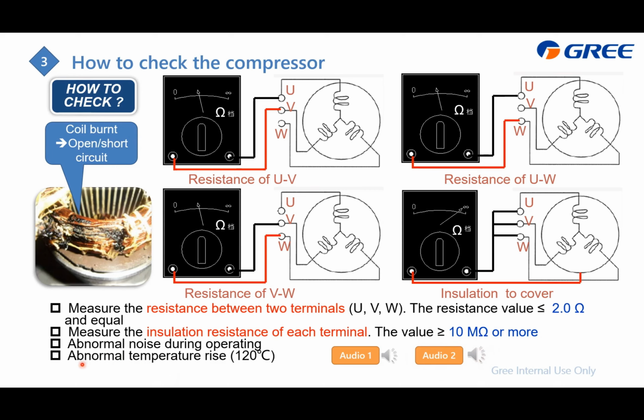And next is to judge from the temperature rise, which applies at any time. If you find that the compressor temperature anywhere is more than 120 degrees, you can also judge that the compressor is malfunctioning.